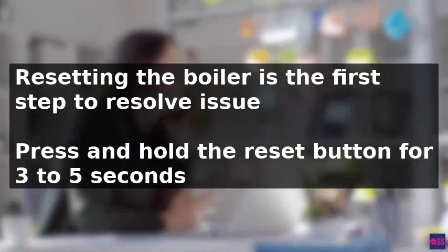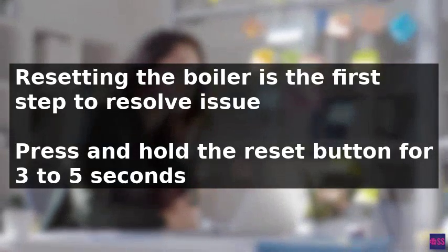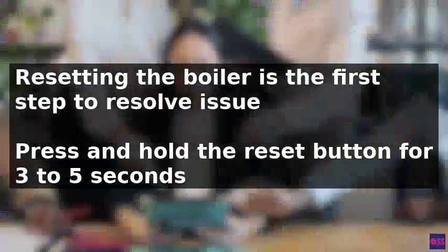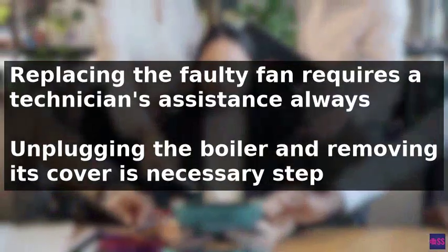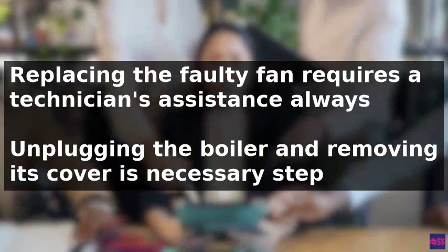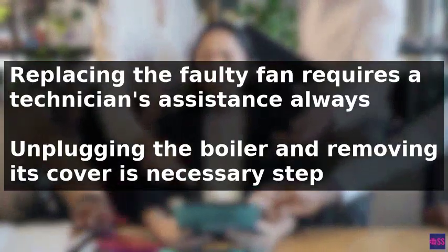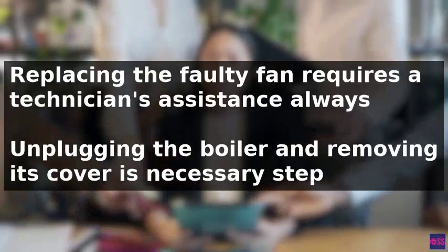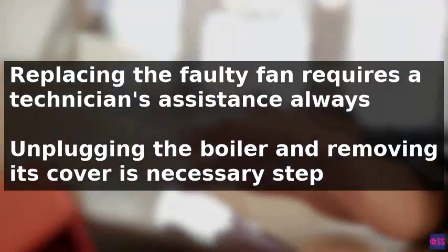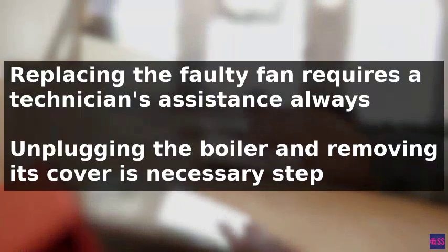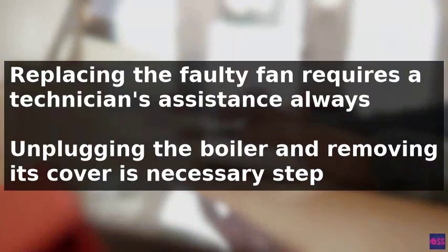If the issue remains, replacing the faulty fan may be necessary, a task that requires the assistance of a technician. The process involves unplugging the boiler, removing its cover to access the internal components, disconnecting the fan's plug connector and electrode connections, and then pulling out the fan assembly.